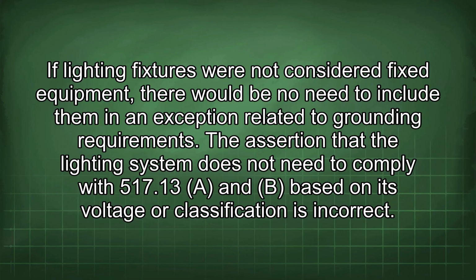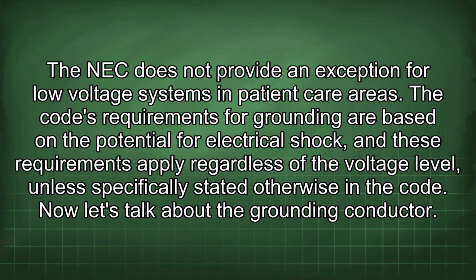If lighting fixtures were not considered fixed equipment, there would be no need to include them in an exception related to grounding requirements. The assertion that the lighting system does not need to comply with 517.13 A and B based on its voltage or classification is incorrect. The NEC does not provide an exception for low-voltage systems in patient care areas. The code's requirements for grounding are based on the potential for electrical shock, and these requirements apply regardless of the voltage level, unless specifically stated otherwise in the code.